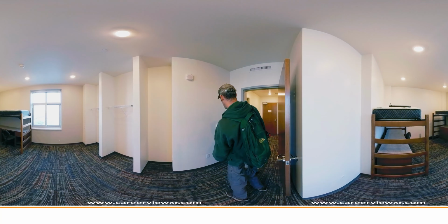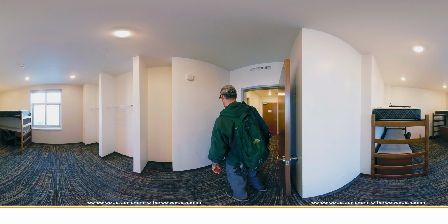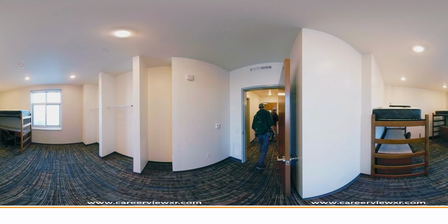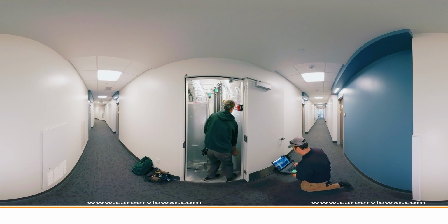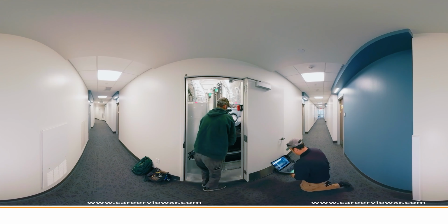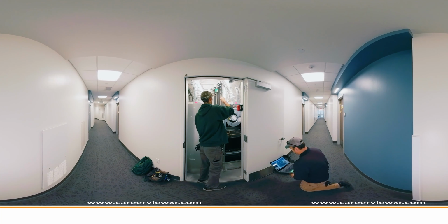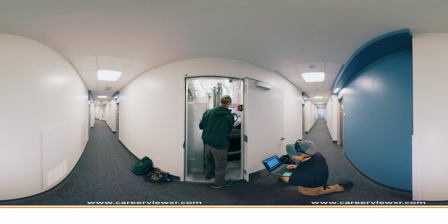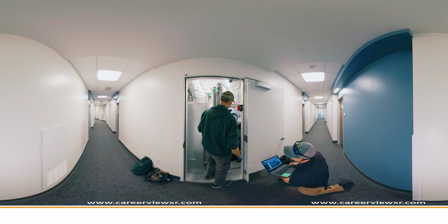They don't hear the fan running and decide to check on it to see if that is the cooling issue. Andy takes the panel off the fan coil unit. He double-checks the voltages with a multimeter tool. He notices one of the wires is not plugged in all the way. He checks the pins and plugs the clip back in, and the fan starts up.